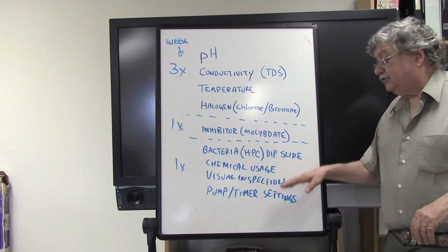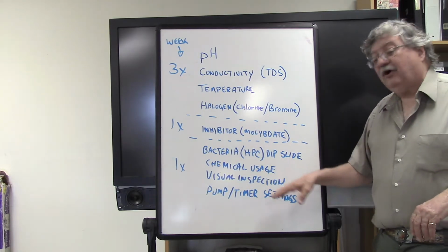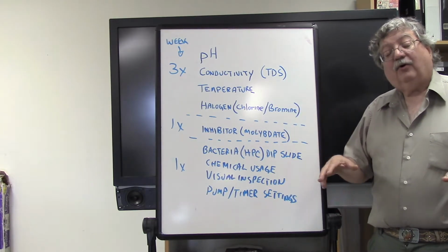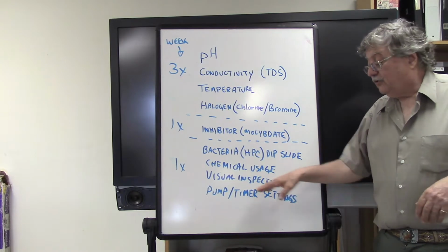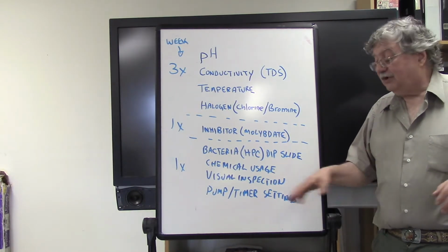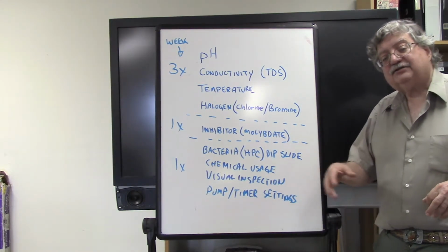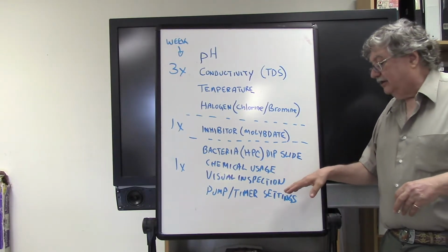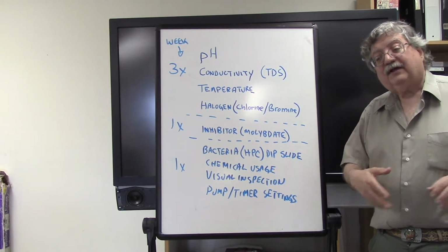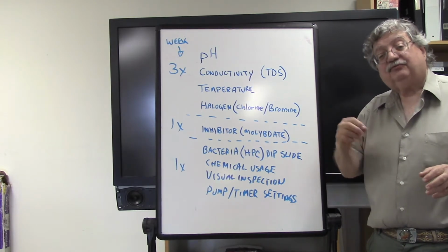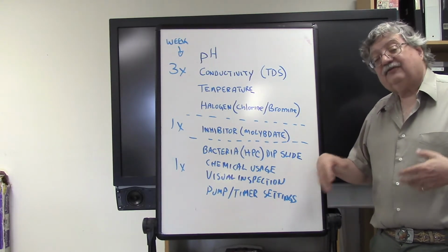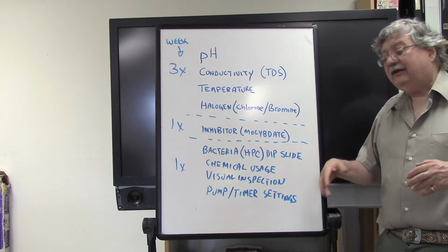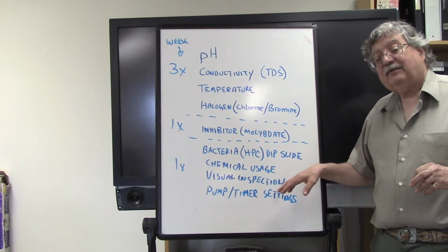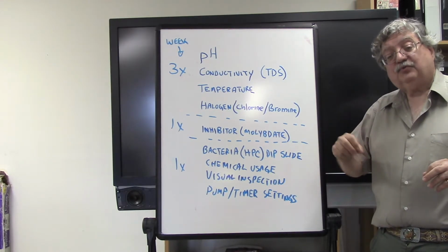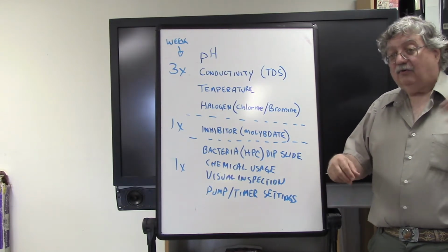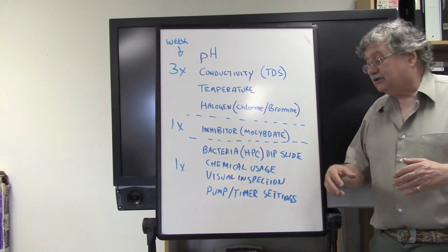You should also record the pump and timer settings on your controller. Often, if things are working well, you'll record them with help from your water treatment company to get the right readings: what percentage the pumps are on, what the timer settings are, and so on. Week to week they usually won't change, but you should still record them. Occasionally, if there's an excursion with not enough chemical being fed, they'll alter those settings, and you should update what the current setting is each week.